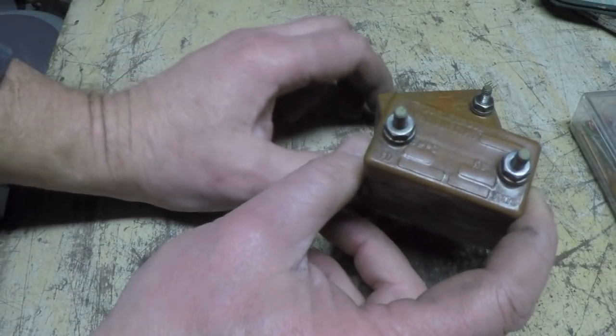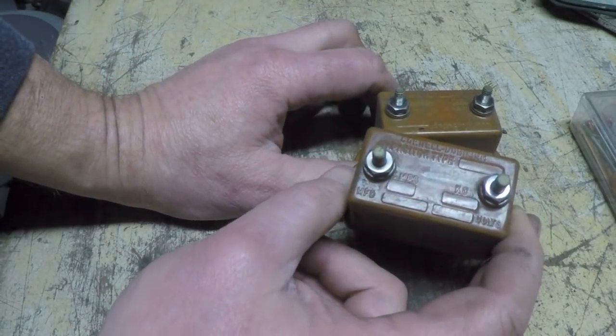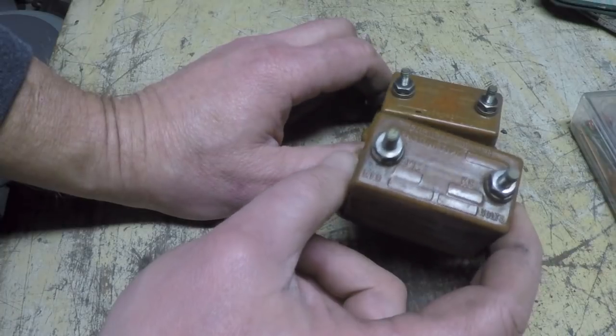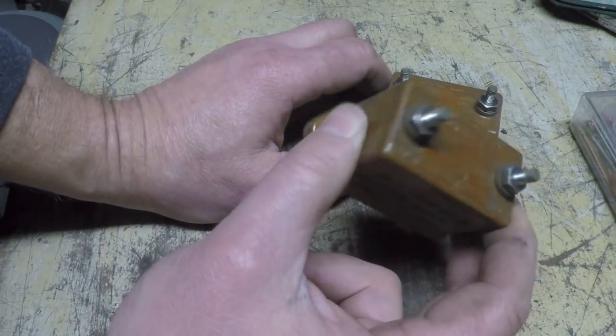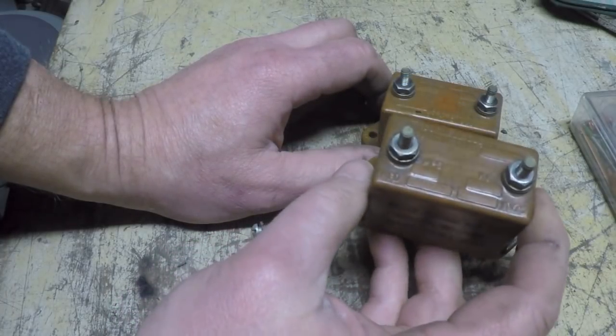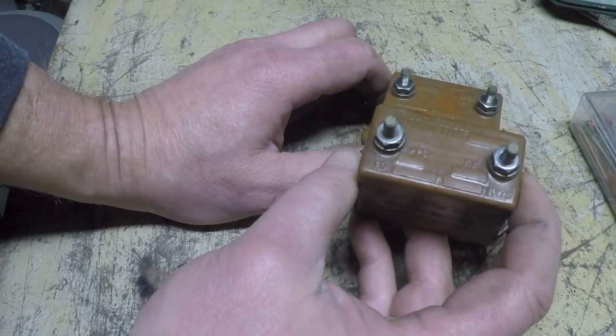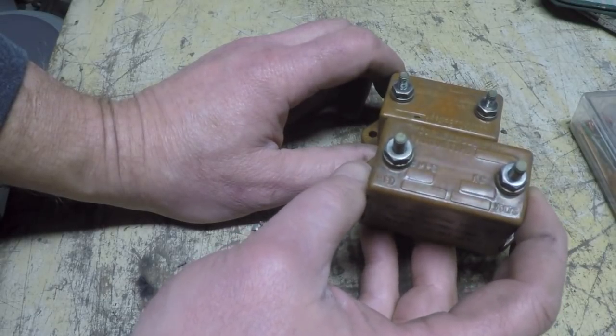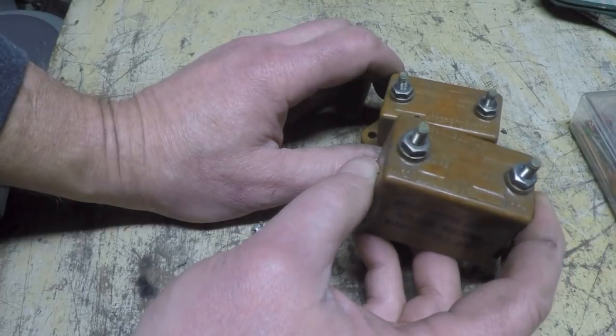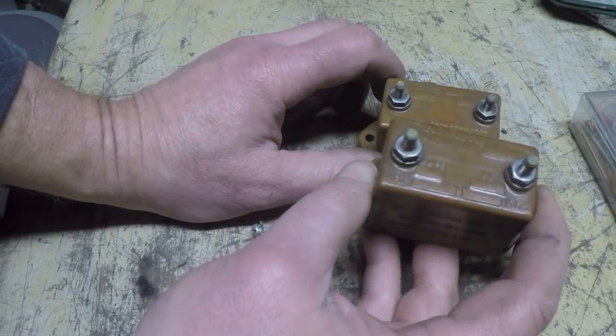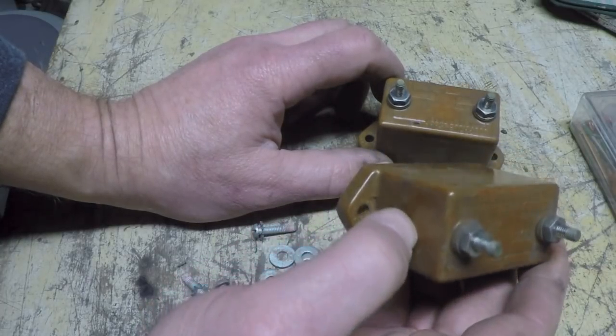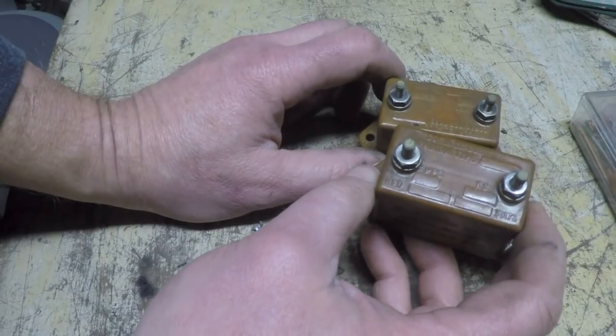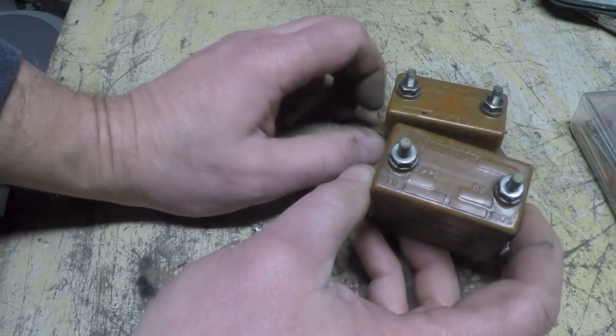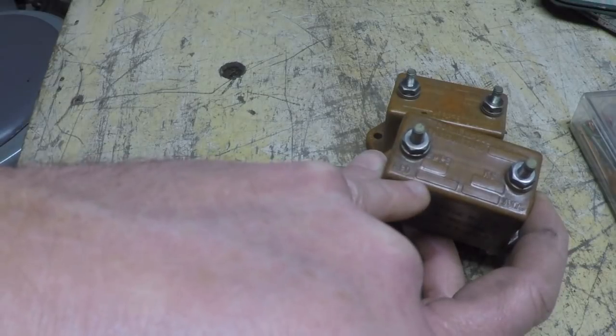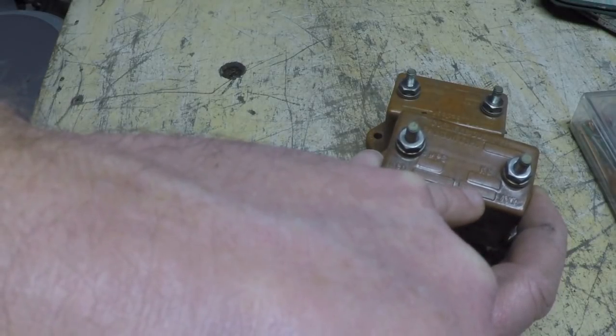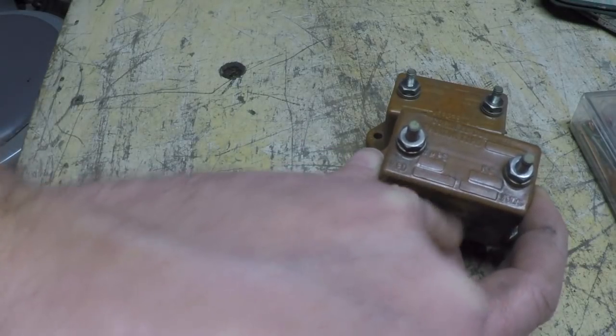Now, the dirty little secret about these is out. It's all over the internet. It's well documented that these are 0.002 microfarad caps, and I believe they were 6 kV originally rated for, either 4 or 6 kV, but you can find it online. But the general consensus is that at this point you want to replace these with something even more robust. We don't want to mess with the microfarads. We want to have a higher voltage rating if possible.